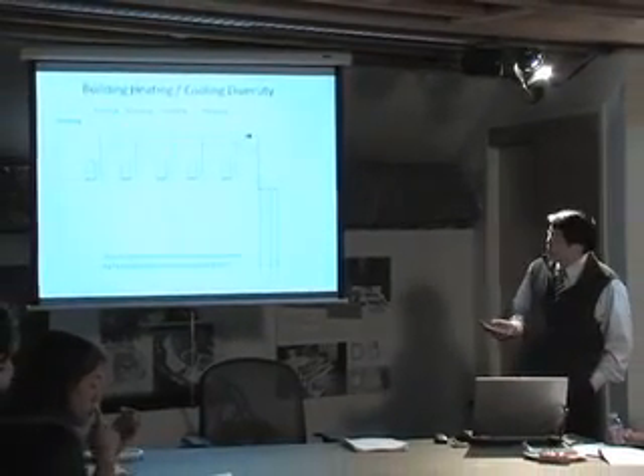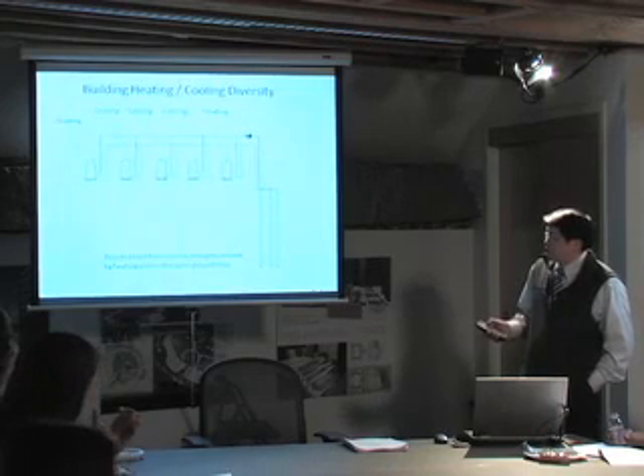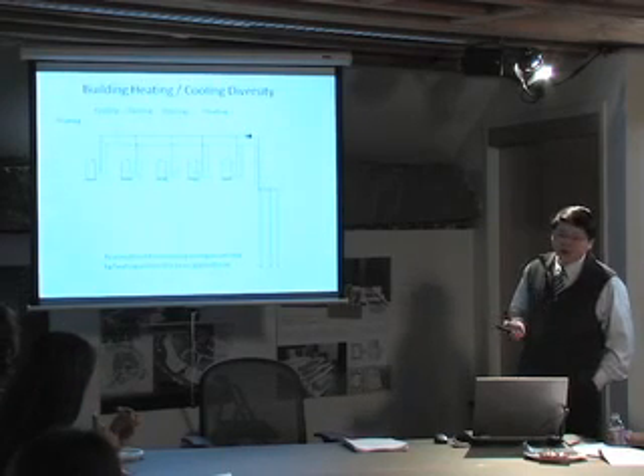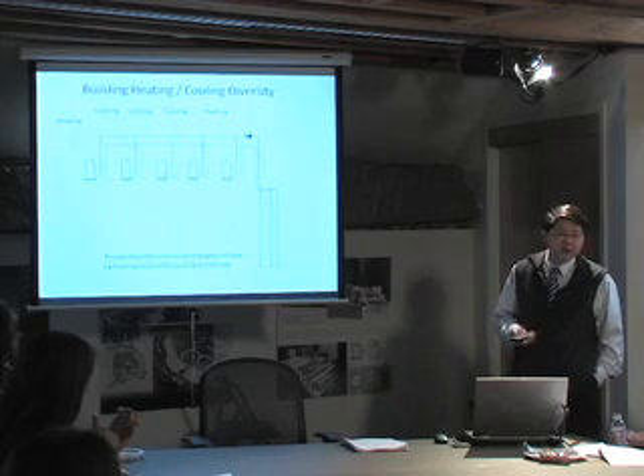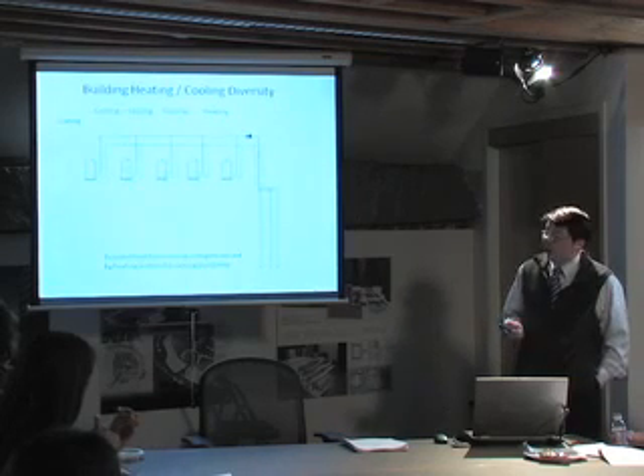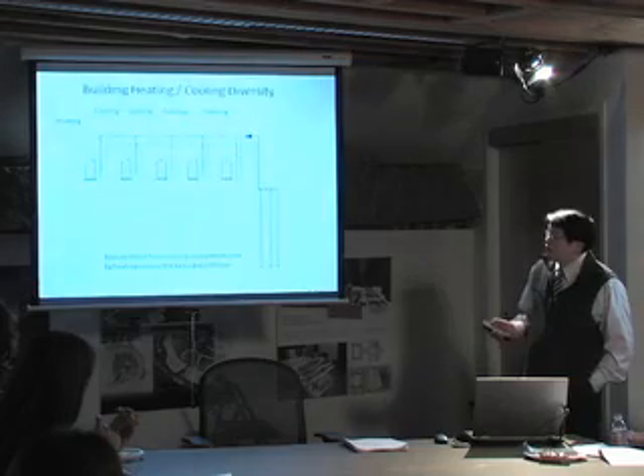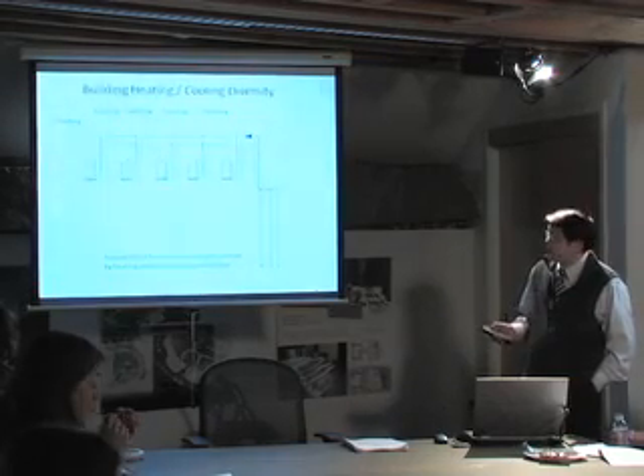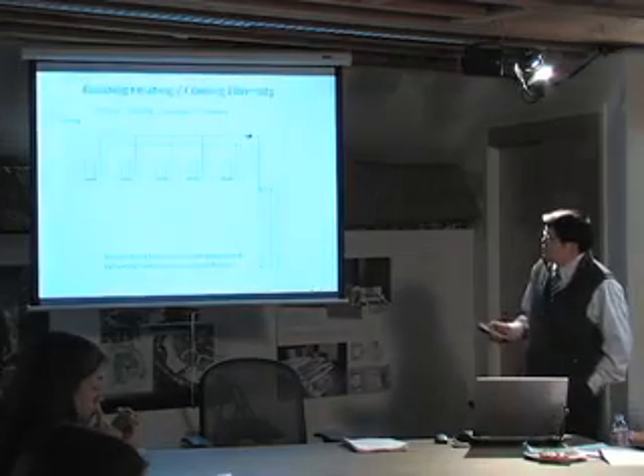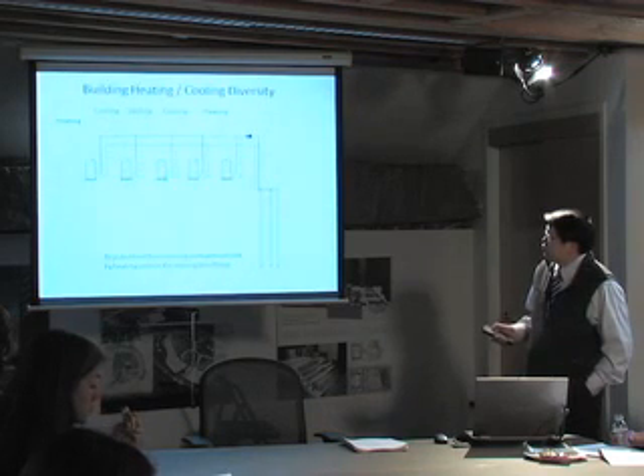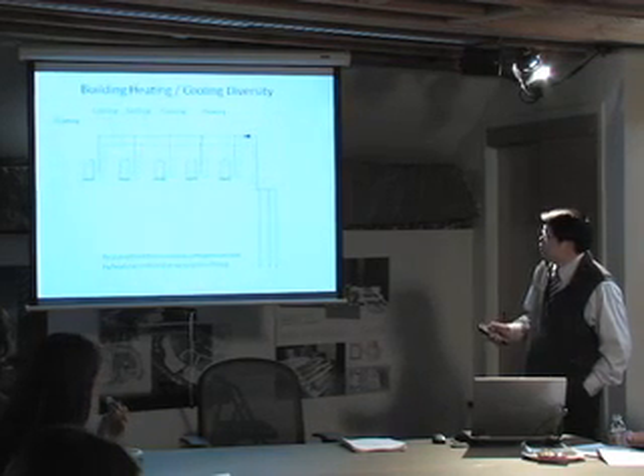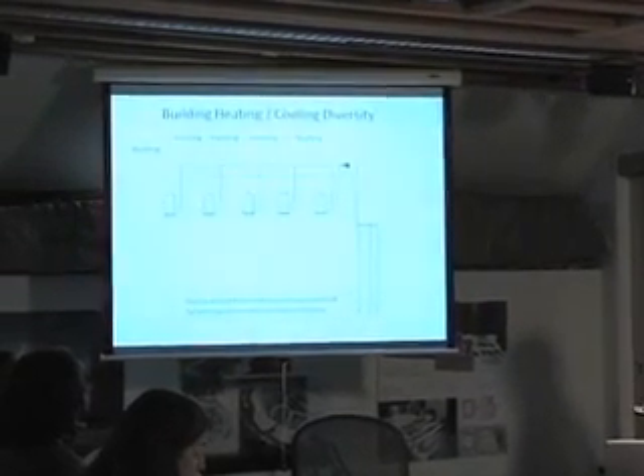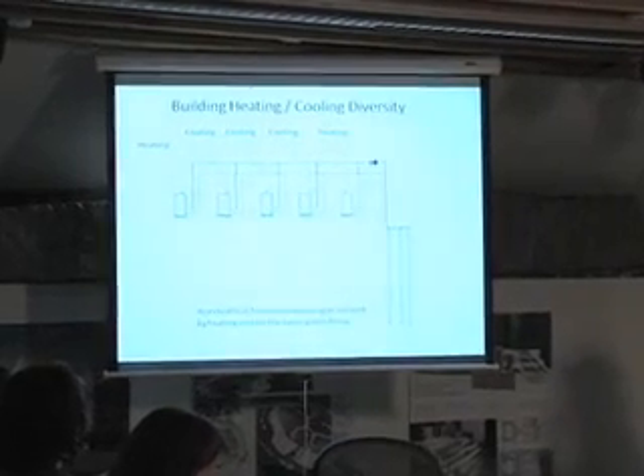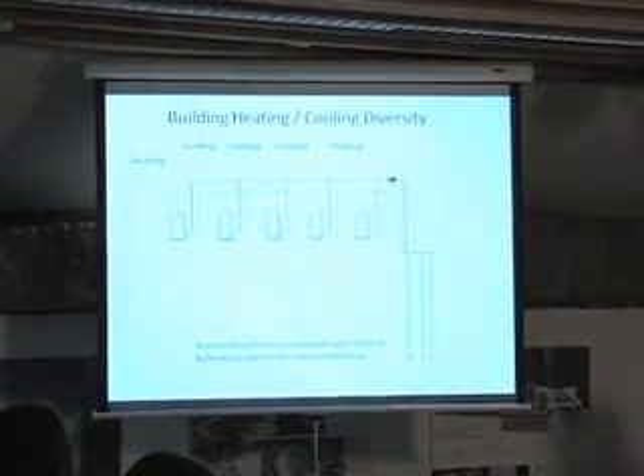Now, another reason why the geothermal heat pump system is efficient. Let's say you have a big building. In a big building, the interior zones never need any heating throughout the year. You always need cooling. But the perimeter zones need heating during the heating season. So when the heat pumps are running, the units that are doing cooling reject heat into the same ground loop, and that heat gets utilized by the heating units. So the waste heat gets utilized. That's partly why it's so efficient.